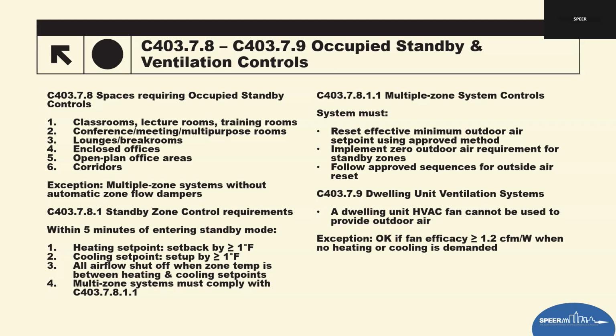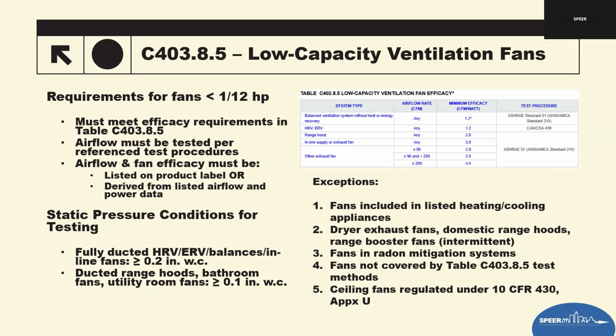Field inspection tips. We've got to test the sensors activation, that verify that 5-minute response. Confirm airflow shuts off during standby. And then check BAS trend logs for outdoor air reset. And then also you can measure fan efficacy if using HVAC fans for ventilation. You'll have to do that, what's the CFM, and then divide it by the watts and see if you get that 1.2 CFM per watt. Otherwise, it is not compliant.